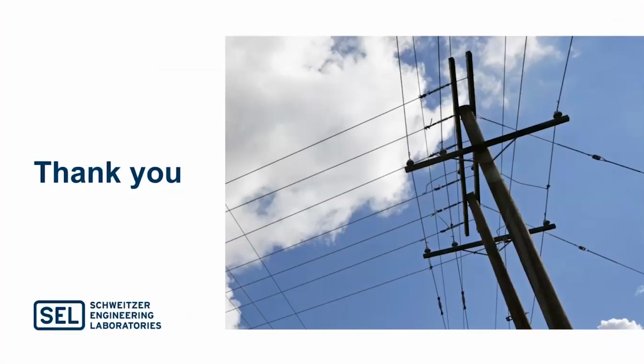Thank you. We have a question, Jared. What are the elements that allow blocking reclosing for portions of a line? It's just the traveling wave fault location. The traveling wave fault locator is going to say the distance of where the fault occurred is X, right? And if that fault location is determined to be within your blocking zone, then you're going to block. So it's all just the fault location.